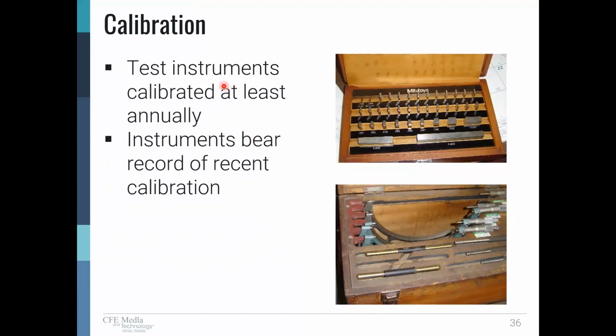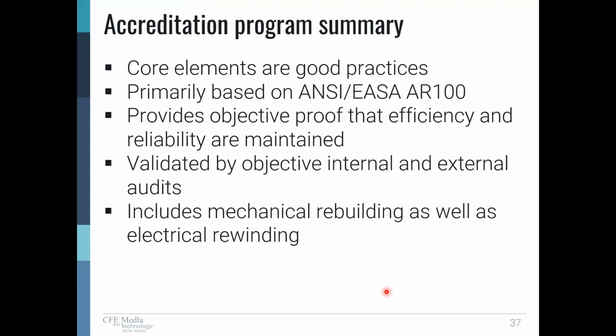With calibration, we have the test instruments that are calibrated at least annually. Example here, some inside micrometers, and we see a label over here that's green and white. That's the calibration label. What we have in the upper photo is a series of gauge blocks. These are very high precision. The micrometer is set up and measures these, which are of an exact known length, much more precise even than the micrometer. And that's part of the calibration process. Some service centers have this capability in-house. Some send them out to be calibrated. All the instruments, mechanical as well as electrical, the ammeters, the voltmeters, watt meters, they're all calibrated.